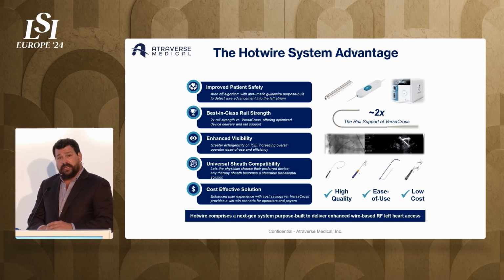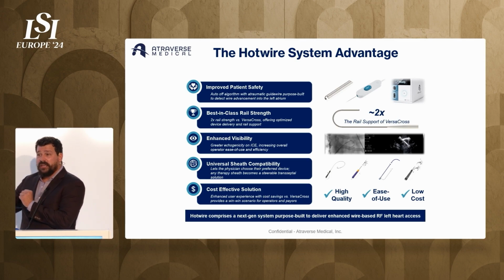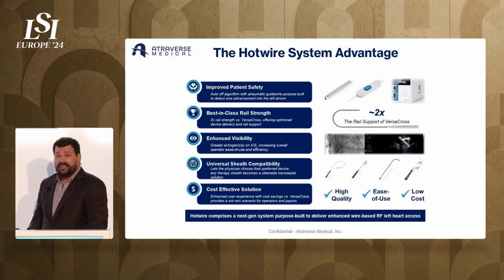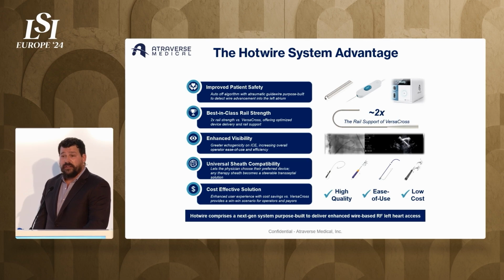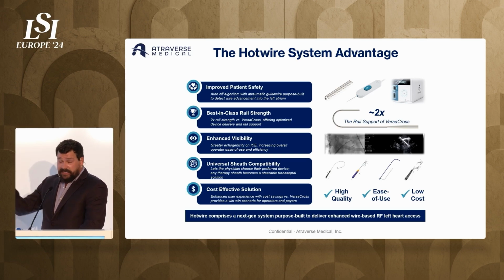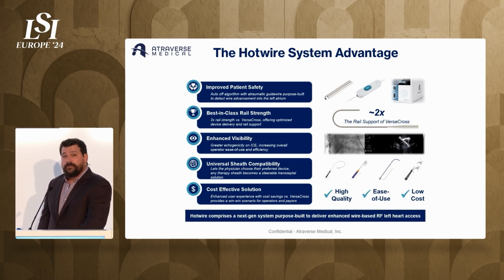Well, we have a unique electrode design for the wire that lends itself to what we call our auto-off algorithm. So when you're positioned to the septum and you cross, within 100 milliseconds, the device can detect a major impedance drop and automatically shuts off to terminate the energy. While the VersaCross is a great product, it's documented in the literature that based on the pre-programmed energy duration settings, 2 or 3 seconds after it cuts, and it cuts very, very well, it can actually cut adjacent and or collateral structures. And again, this is well documented in the literature.